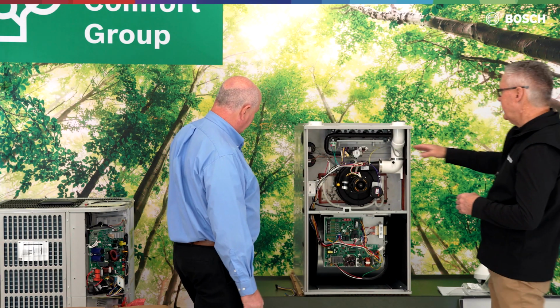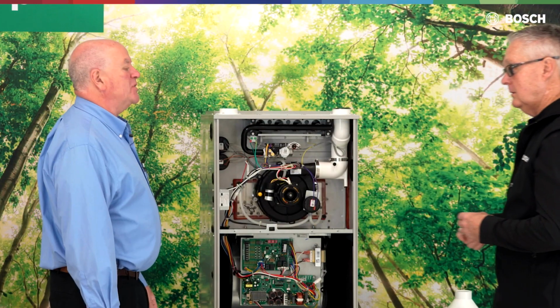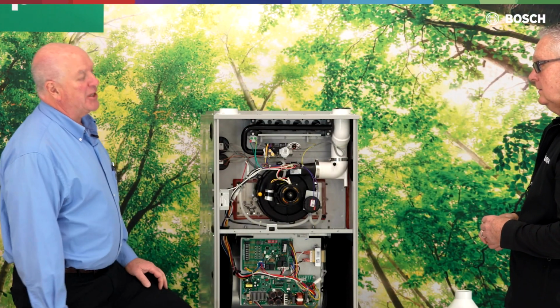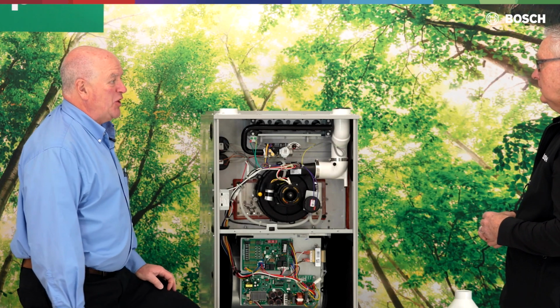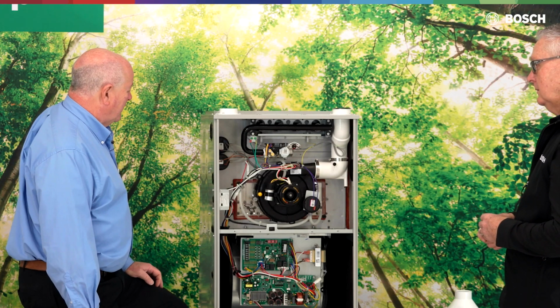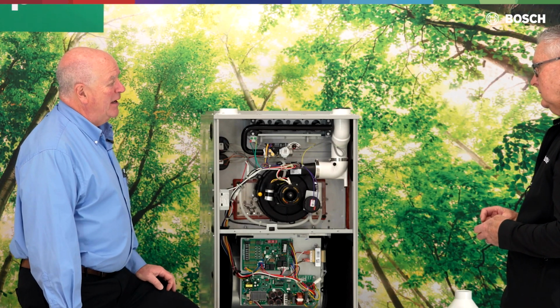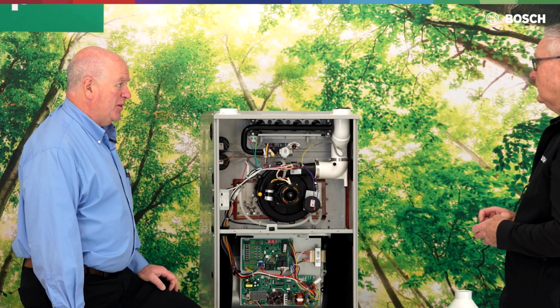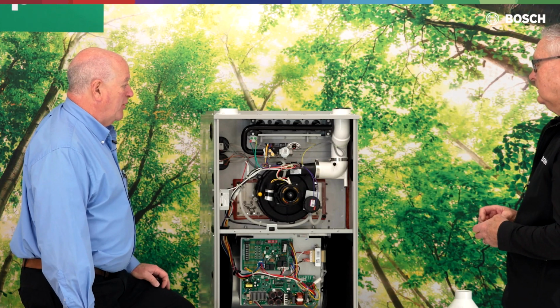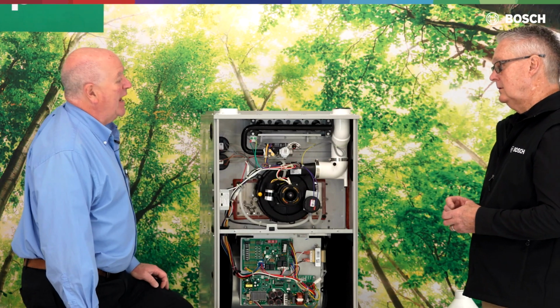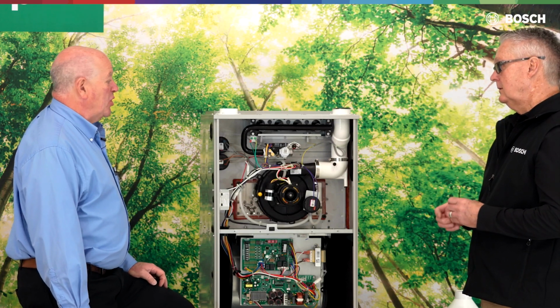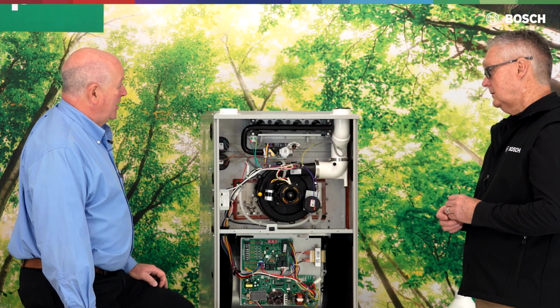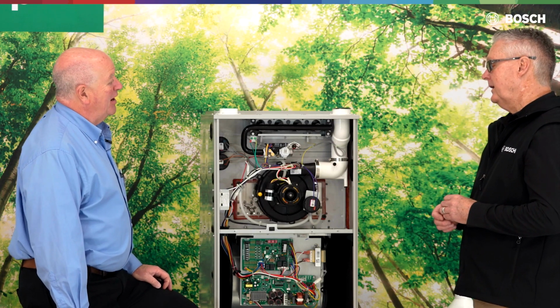What would cause that high limit to trip and open up? Well, there's a couple of things. One is irregular gas pressure, or higher gas pressure than what we should have. Our biggest issues are when you convert this from natural to LP, you have to adjust your gas pressure. And if you fire off at 4.5 on low and 10.5 on high, and somehow you go back to natural, you would have a blowtorch in there. It would be very radical.